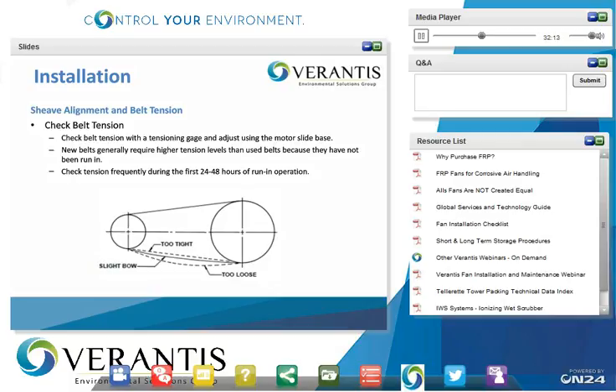In the diagram, if the belts are too tight, the slack side of the belt is going to run pretty well in a straight line. If you have a slight bow to the belt, that's optimal. If the belts are too loose, they're really going to be hanging low, and you're going to end up with belt slippage, and you're going to start seeing belt dust inside the guards. When that happens, you're wearing your belts out. They're going to prematurely fail, and you could also potentially be wearing out the sheaves.